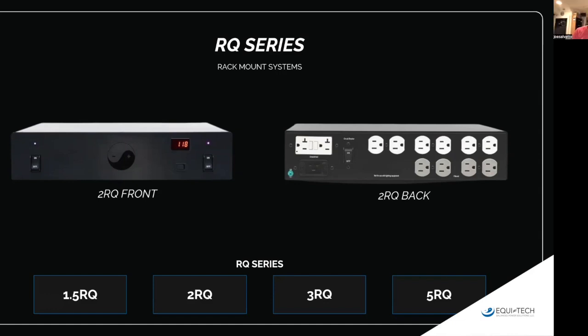No, it's okay, it's 208 to 220 - what do you mean it has to be 240? Well, the 30 amp breaker on that run, which was beefed up for the Mitsubishis, that is not sufficient for anything above a 2RQ. That's right, because those tape machines were 120 volts. But why would it be 30 amps? That's weird, I don't know.